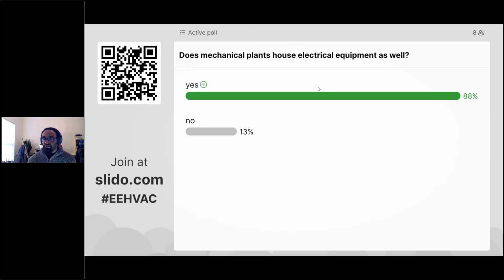You're going to have electrical panels, you're going to have disconnects, you're going to have other items in there, especially for your controls, for any chiller system or any type of air conditioning system. You're going to have control circuit wiring that's sent back to your direct digital control system, whether that's your BAS computer system located on site, or you'll have some sort of remote connection able to send that signal out to wherever the remote site is monitoring that facility. So yes, you will have electrical equipment housed inside of your mechanical plant, but it is for providing the power for the operation of those different systems in there. So good choice there.